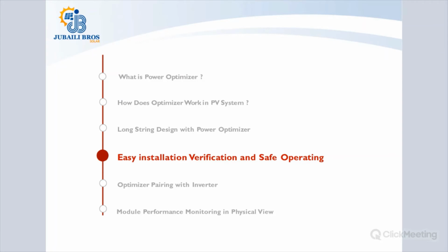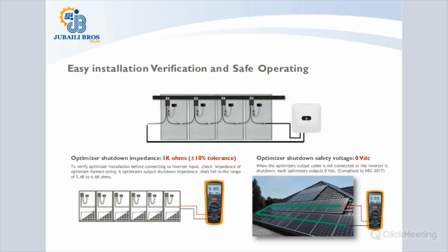Okay, so let us wrap up quickly. Ease of installation verification, and then the safe operation mode of the inverters. That is the next topic. Here we are taking a look at a system that has been beautifully connected with PV optimizers. As we explained, the output of each module is connected to the optimizer, and the optimizers connect with each other serially to the inverter. If you want to check, it is easy to see whether the connection has been done properly or not. The maximum impedance of each PV optimizer is 1K ohms, that is 1,000 ohms. So you can just test the open circuit voltage and impedance of the system.